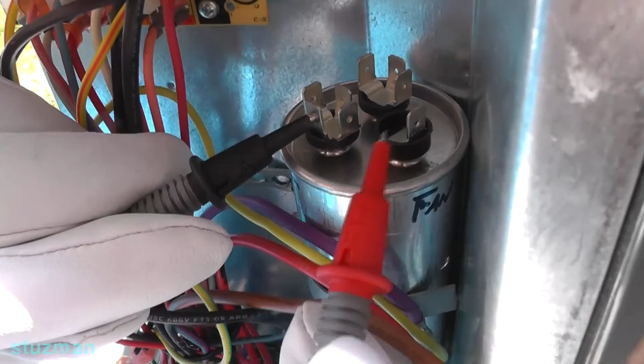Turn the capacitor just a little bit so I can see the readings over here on the side. Right here is our common terminal. This over here is our fan terminal. So this is what we're going to check first. So we'll look up there at the meter. What do we got? 4.93. All right, 4.93 microfarads, okay?